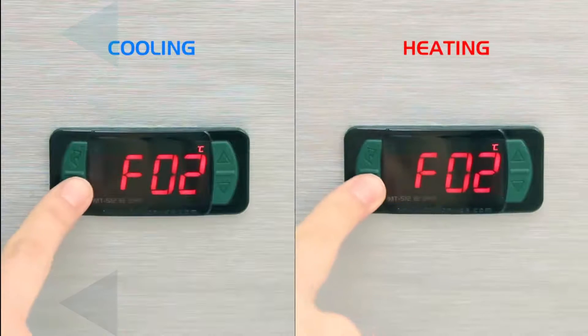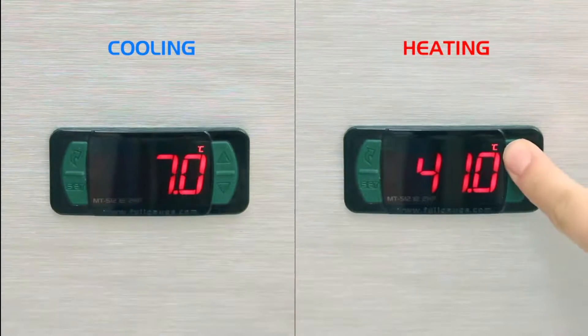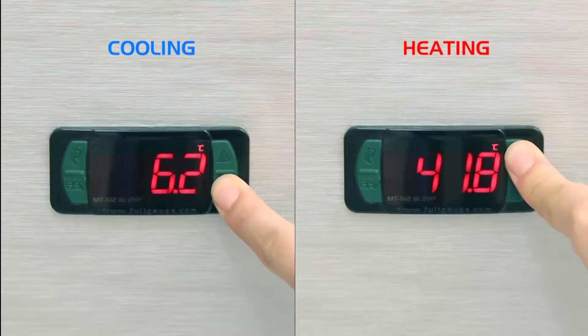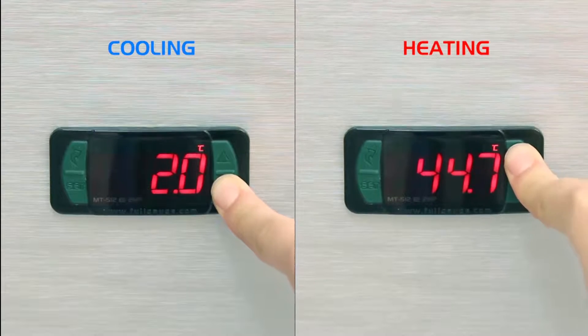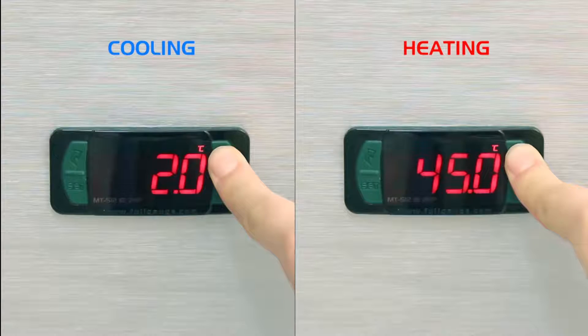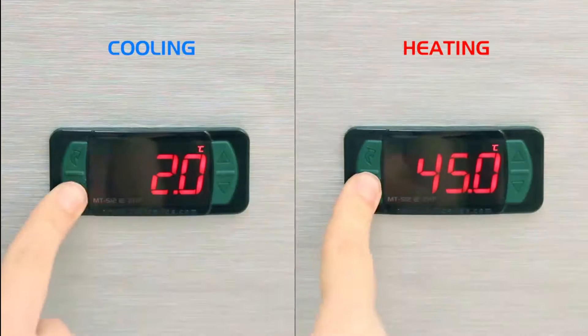F02 Set point. Set point is the temperature we want to keep. It's also the point where the load control relay is turned off. In the examples, we adopted a set point of 2 degrees Celsius in cooling and 45 degrees Celsius in heating.